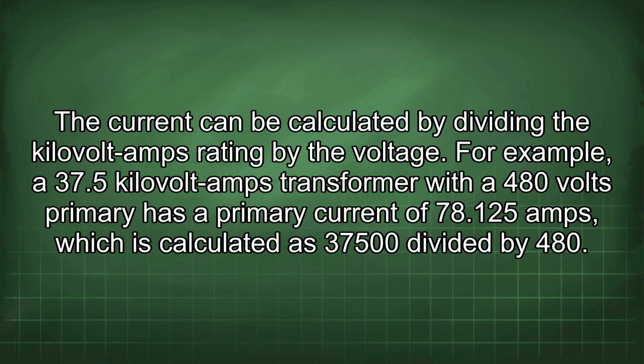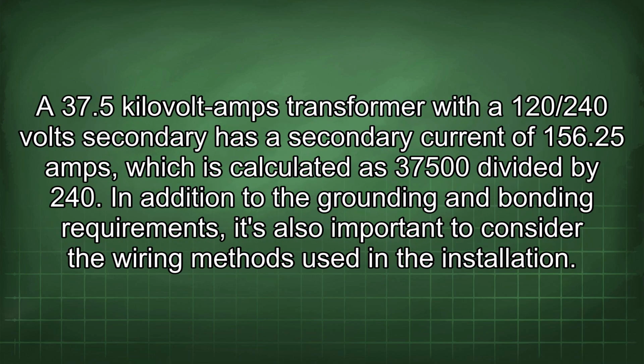The current can be calculated by dividing the kilovolt amps rating by the voltage. For example, a 37.5 kilovolt amps transformer with a 480 volts primary has a primary current of 78.125 amps, which is calculated as 37,500 divided by 480. A 37.5 kilovolt amps transformer with a 120/240 volts secondary has a secondary current of 156.25 amps, which is calculated as 37,500 divided by 240.